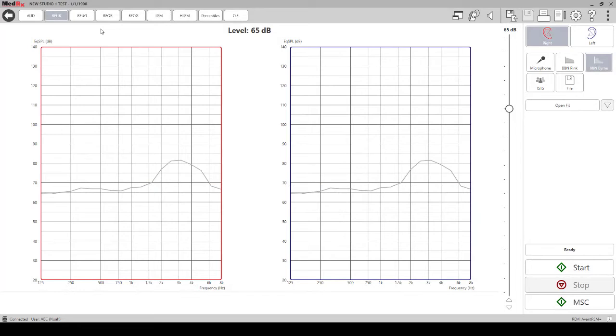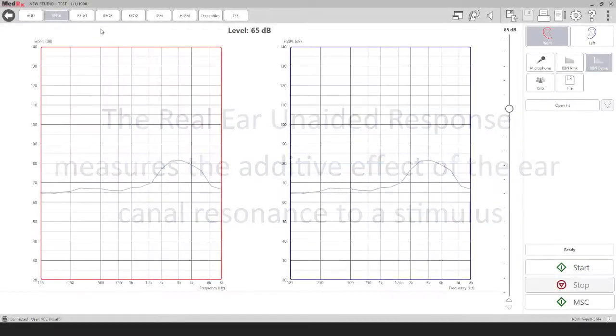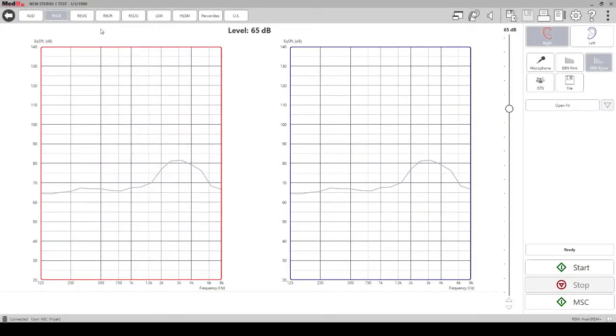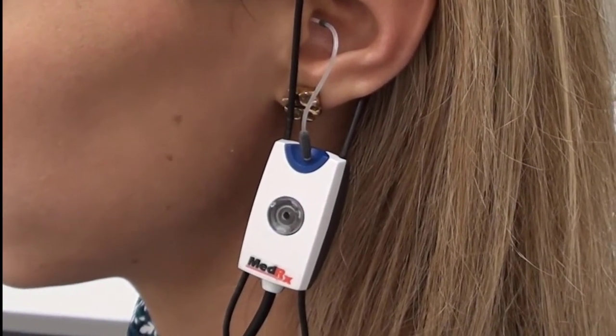If there is a dip in your measured REUR curve at 6 and 8000 Hz that typically indicates poor probe tube placement. The real ear unaided response measures the additive effect of the ear canal's resonance to a stimulus. When measuring the REUR, the probe tube is in the patient's ear without the hearing aid.